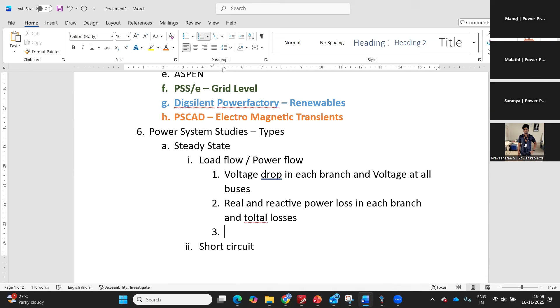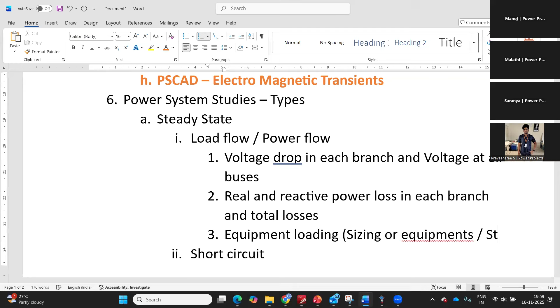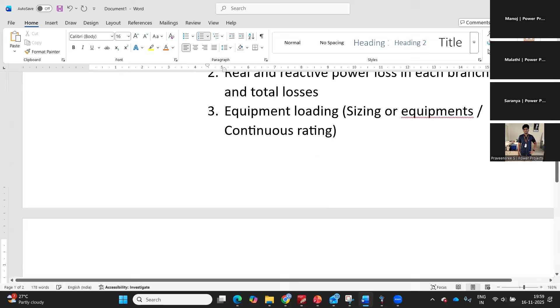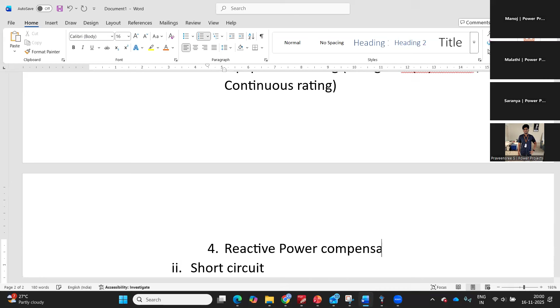Why do you need to perform a load flow? To find out voltage drop in each branch, voltage at all buses, real and reactive power loss in each branch, total losses, equipment loading of each branch or sizing of equipment, continuous rating of equipment, and reactive power compensation studies needed - meaning what capacitor rating is needed, or what shunt reactor is needed.